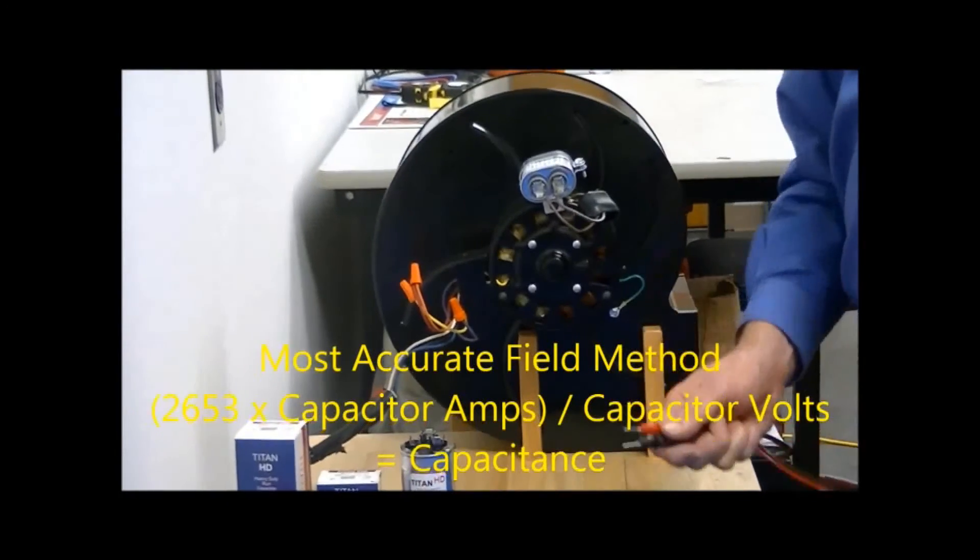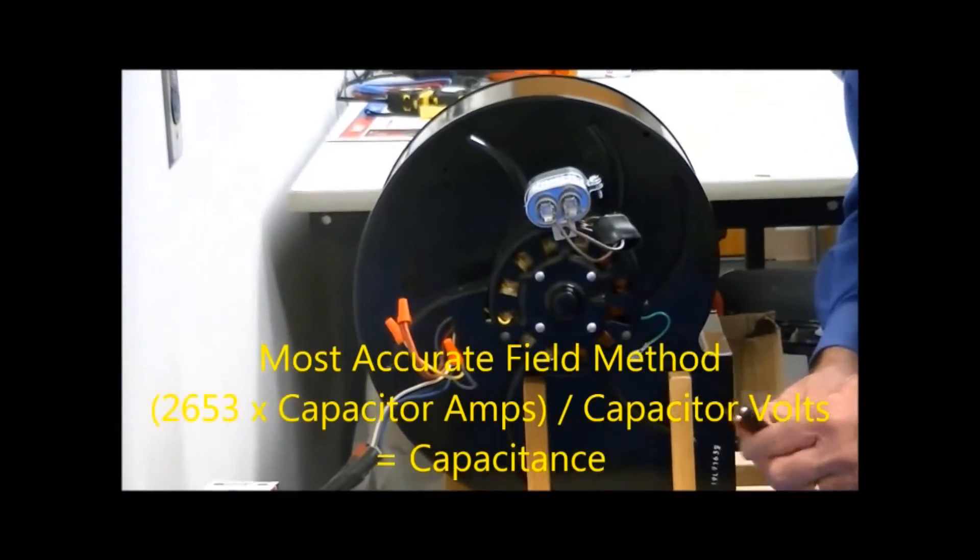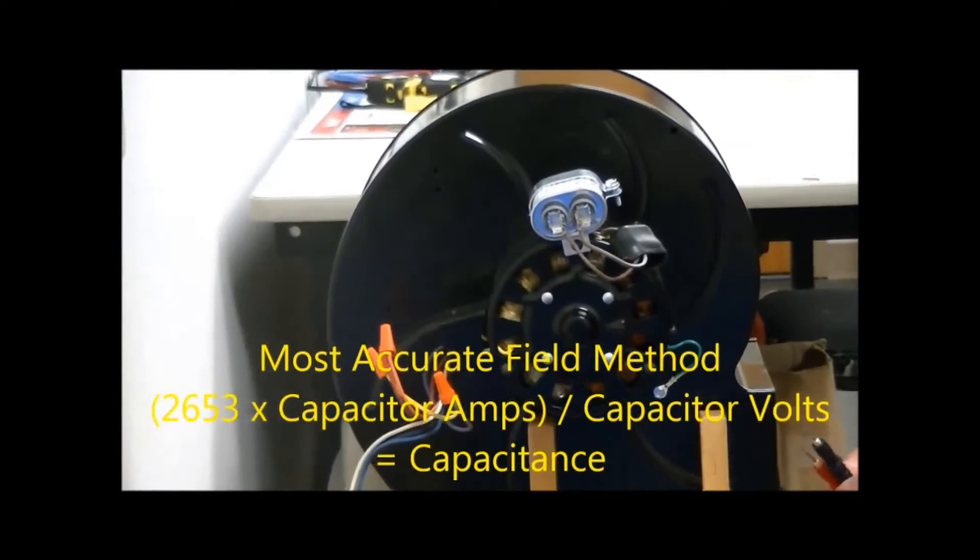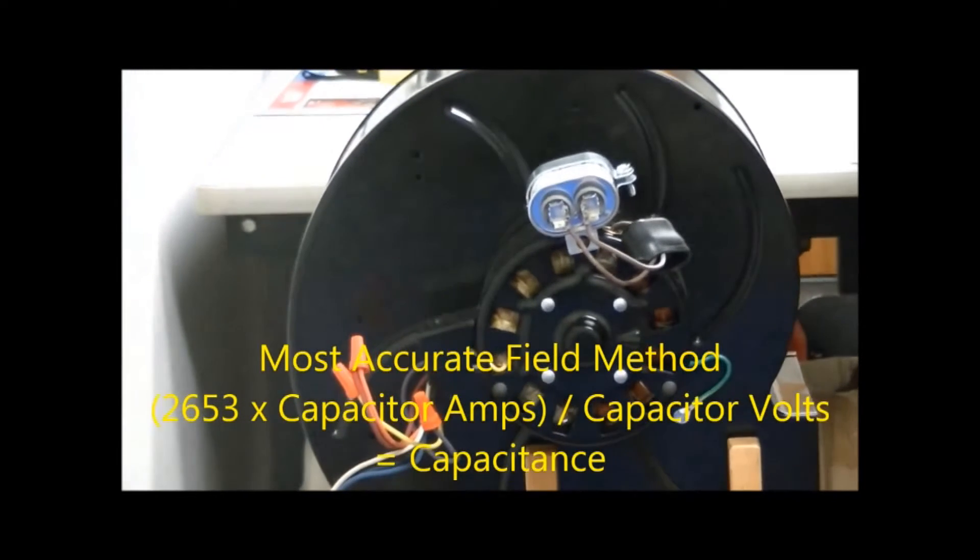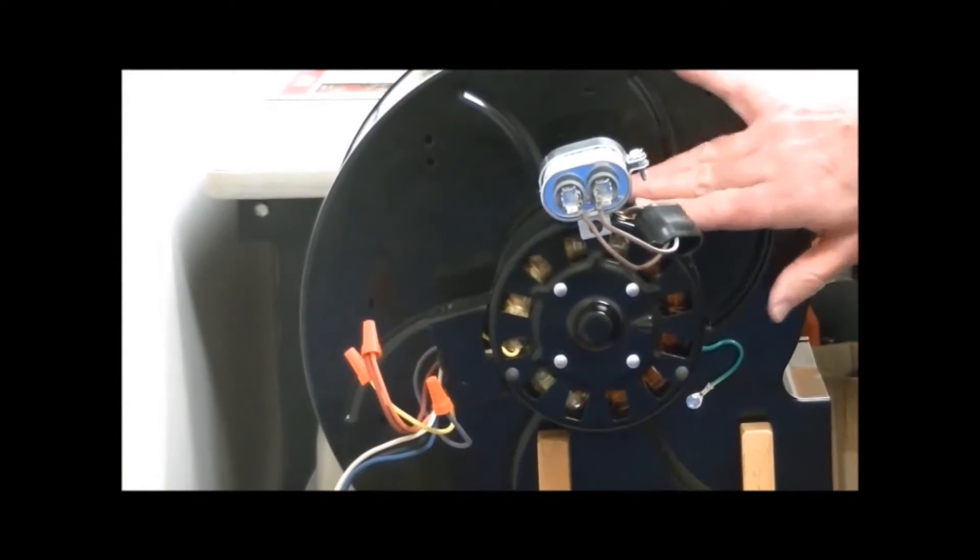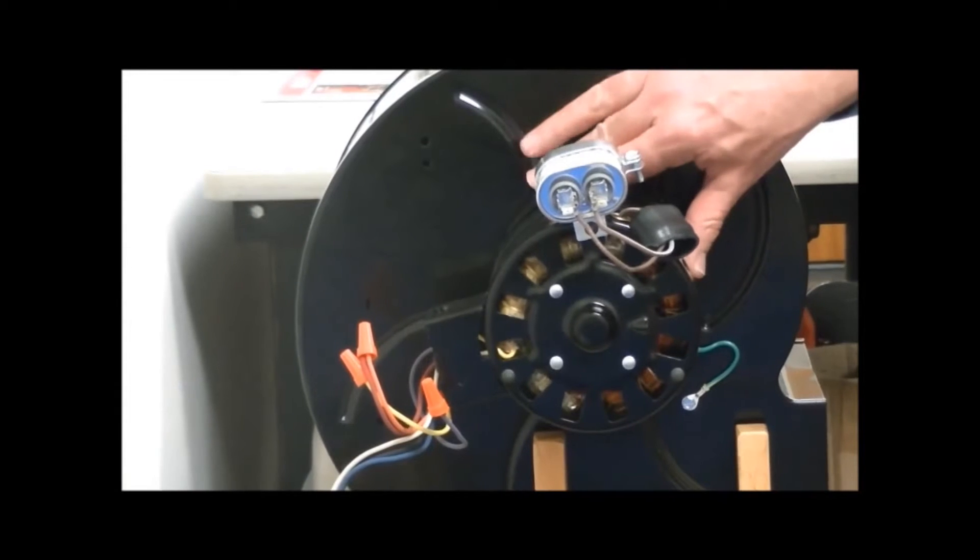We'll use the formula 2653 times capacitor amps, divided by capacitor volts, to see what the capacitance is that's actually going to the motor.